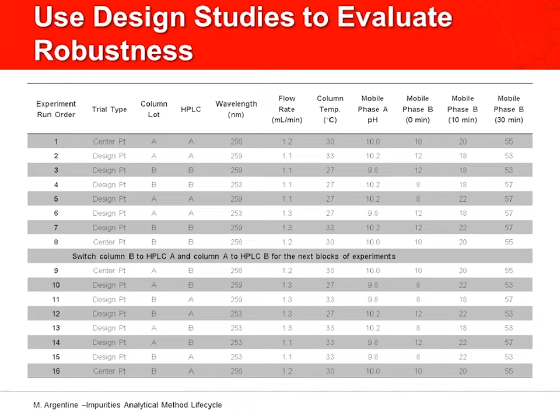And what we find is, as expected from our modeling information, that critical peak pair 1 is in fact fairly sensitive. The lowest resolution happened under a set of experiments that did have very high gradient-related organic conditions that we would have predicted would have minimized that resolution, and we saw that drop as low as 1.1. But in all other instances, resolutions were 1.5 or greater, and in fact, typically as high as 2.5 to over 4. Meanwhile, peak pair 2 really was fairly high to begin with and really didn't change throughout that entire set of experiments.